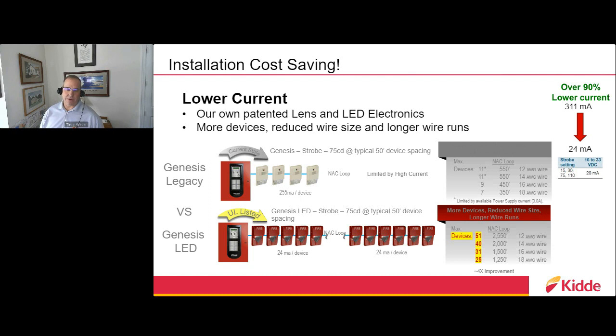So if you had a fire inspector show up to your property to do the inspection, and they realize you installed a 15 candela device, or set it at 15 candela, and it needs to be a 75 or 110, all you have to do is change the switch. You don't have to worry about going back and redoing battery calculations and voltage drops, and providing the other national paperwork to make sure everything has been installed and engineered properly. You get that opportunity right here with us, to just simply change a switch.